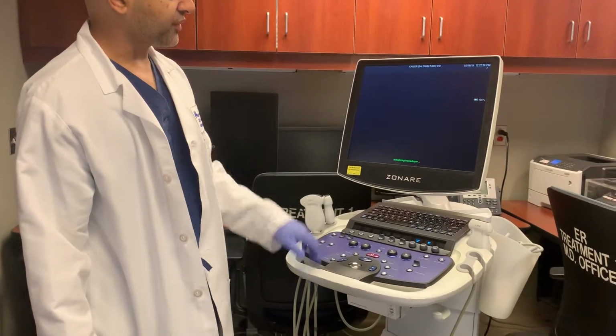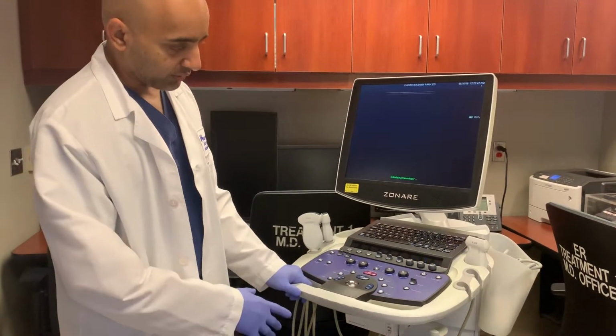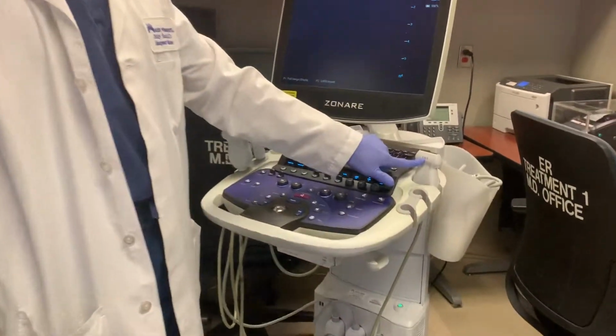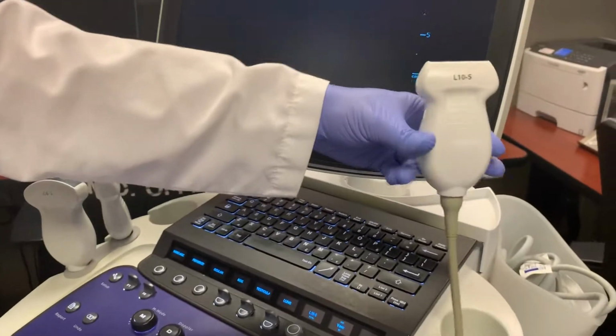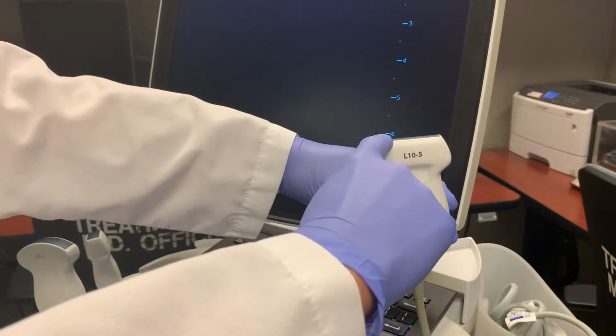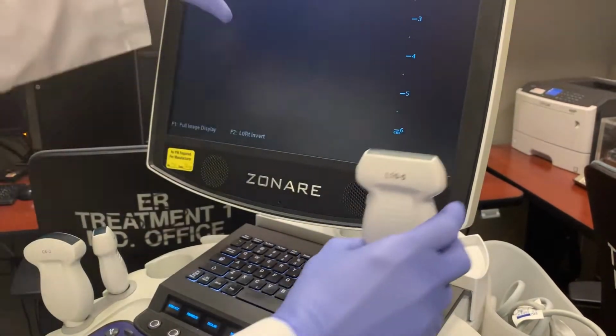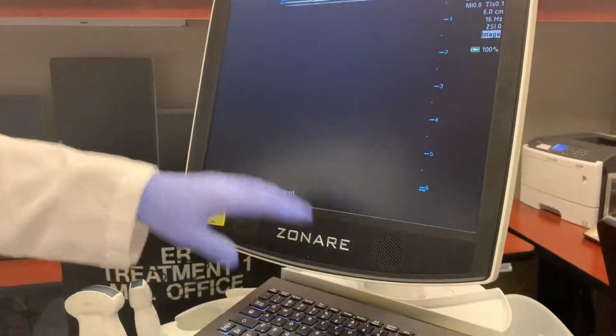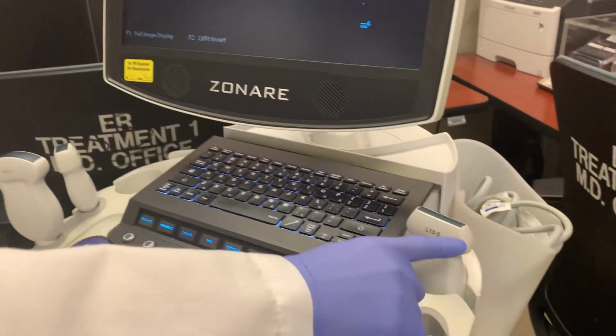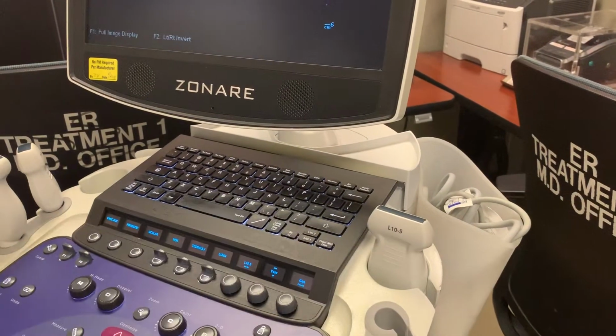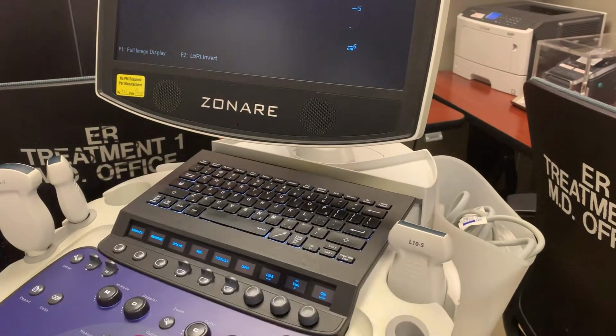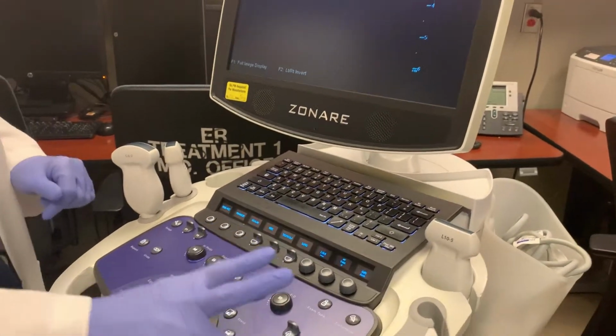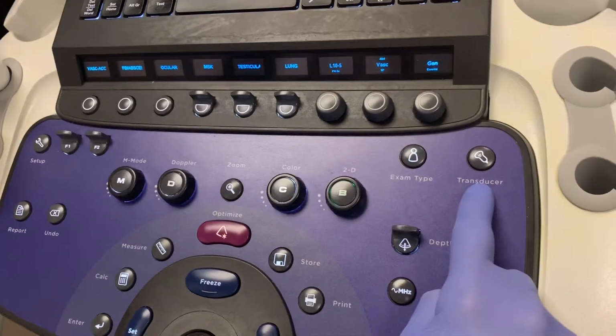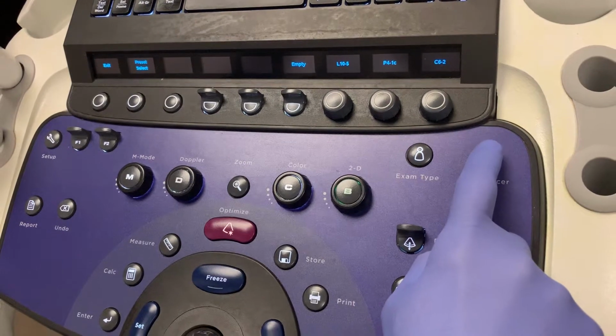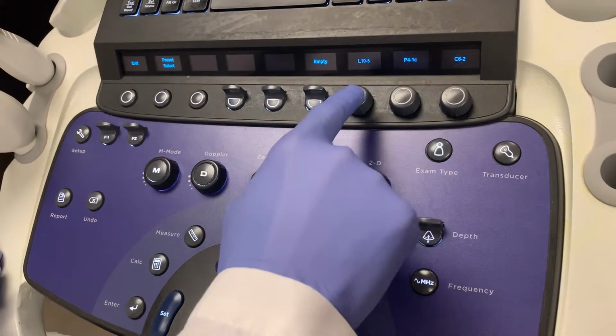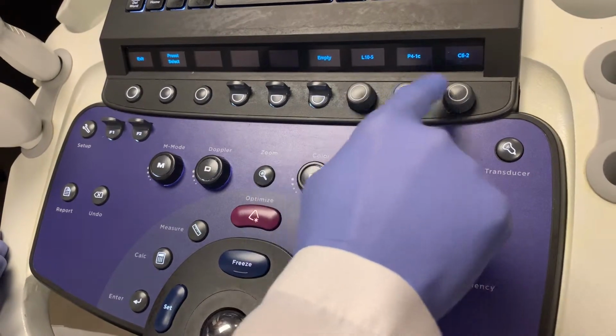Alright, so within a few seconds you'll get your initial image, and in this case the default is our L10 probe. This is the vascular probe, or linear probe. The edge is flat and it has a shallow depth. So you're going to basically be doing vascular access here, foreign bodies, that kind of thing, but mostly vascular access for our purposes. And this is the one that we use for central line placement. Now, if you want to change the probe, there's two ways of doing it. You can hit transducer, and when you hit transducer, this display will change, and you'll be able to cycle through or select which probe you want.